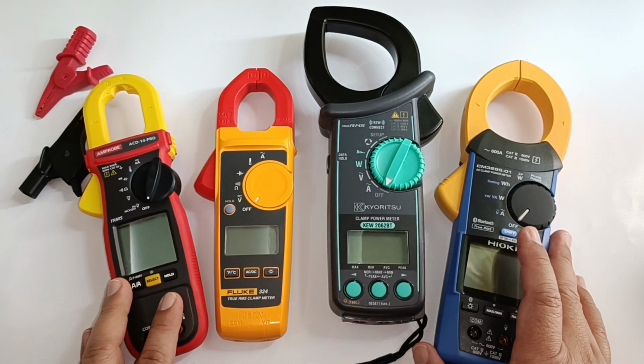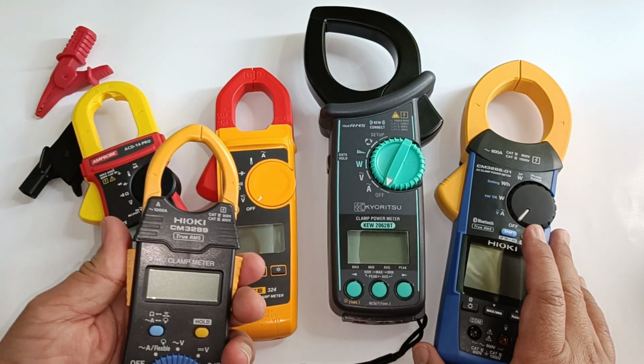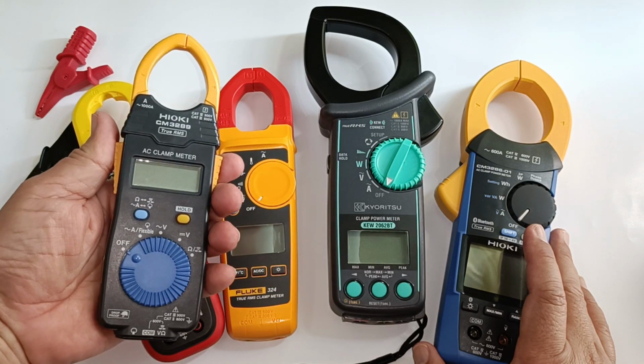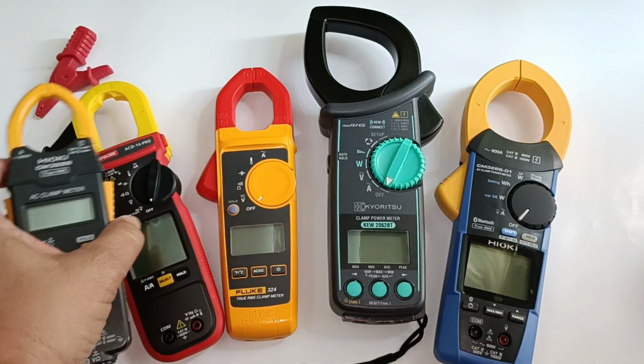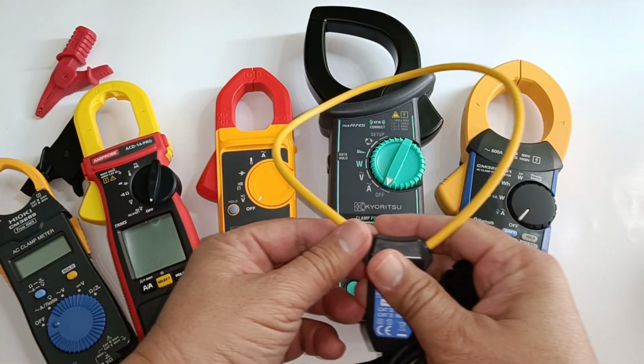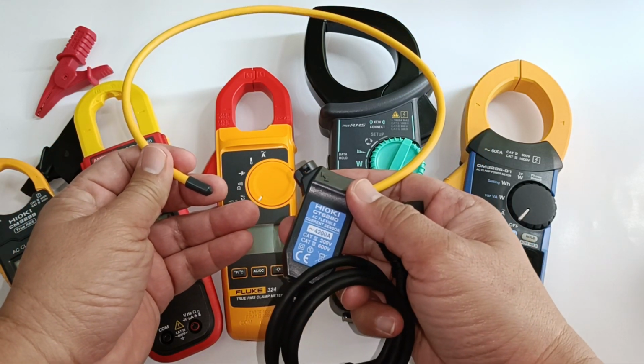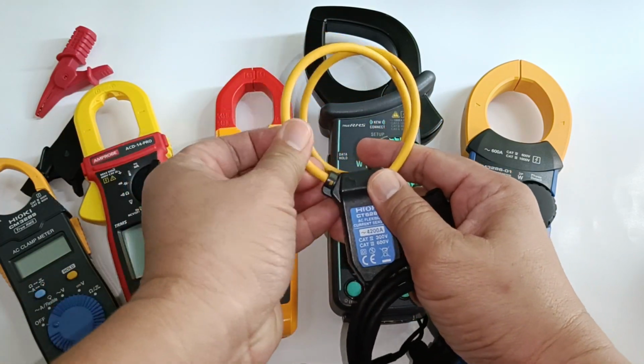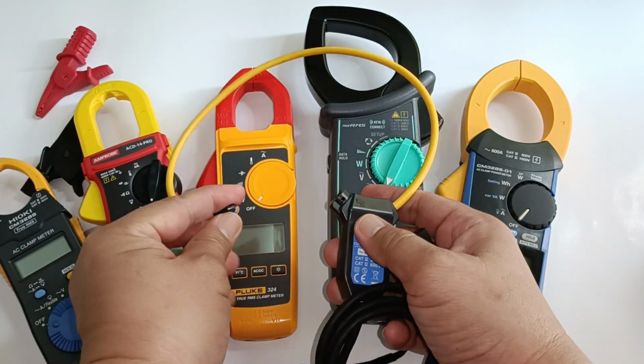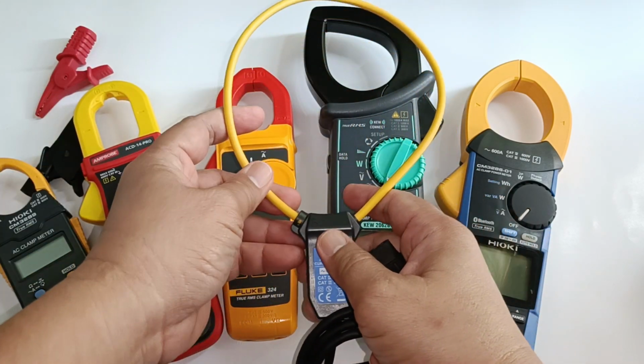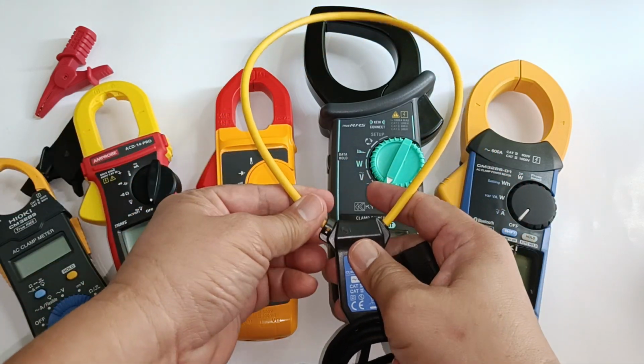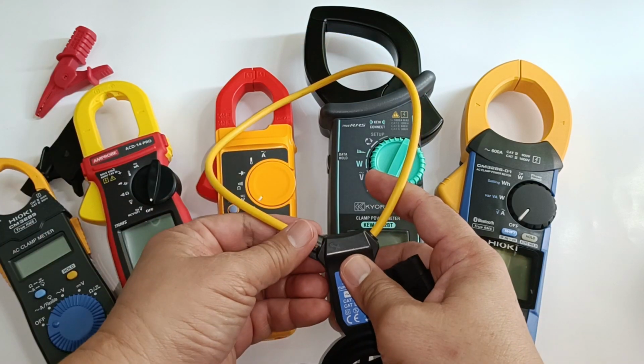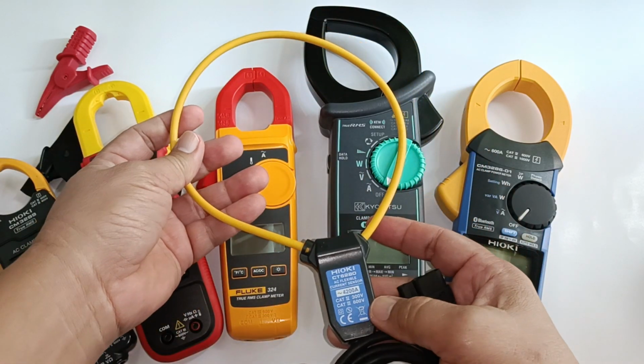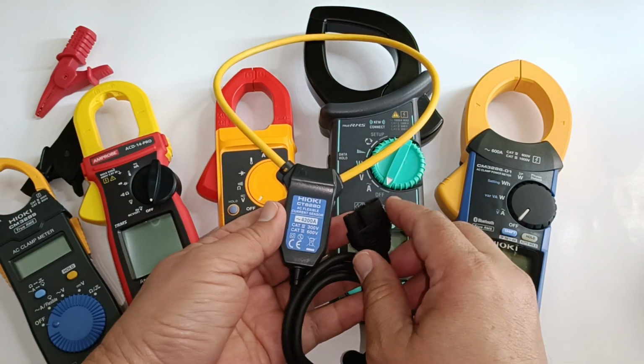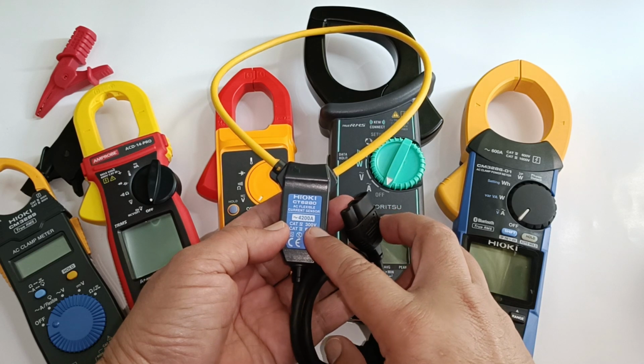This is one of the main reasons why thin jaw design clamp meters are desirable, like this one, the Hioki CM3289, and especially if it can accommodate flexible current sensors like this Hioki CT6280 flexible current sensor, as it allows the sensor to be clamped or wrapped in tight locations or in any kind of bundles of cables, regardless of their shape and size, so long as they would fit within the circumference of this flexible current sensor. Now, this one in particular is capable of measuring up to 4,200 amperes of current.